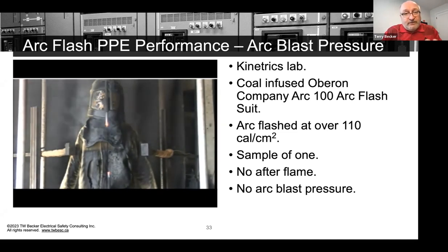This is at the Kinetrics lab in Mississauga, where a lot of the arc flash PPE testing is completed for North America. And they're limited on their fault current. So they had to hold that closed for 2 seconds to get 100 cals of incident energy. So that's not going to be a normal arc flash. We see it sustained like that for 2 seconds. It's the other videos where it happens and it goes away very quickly.